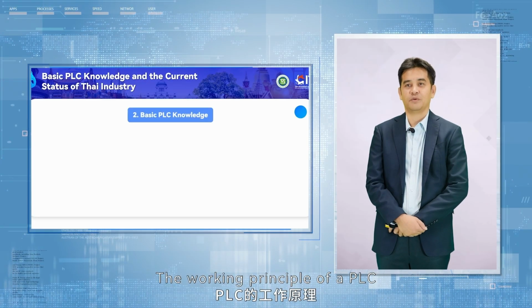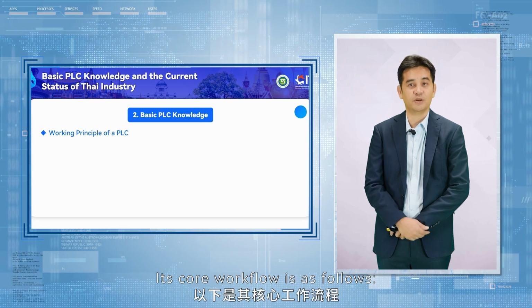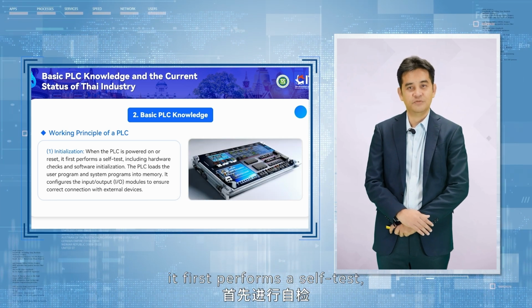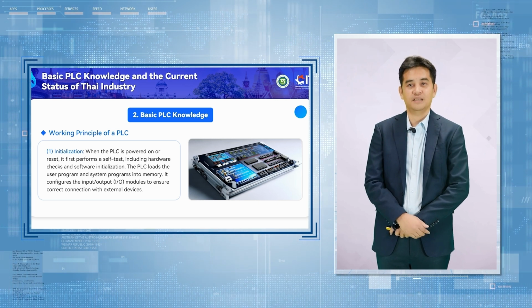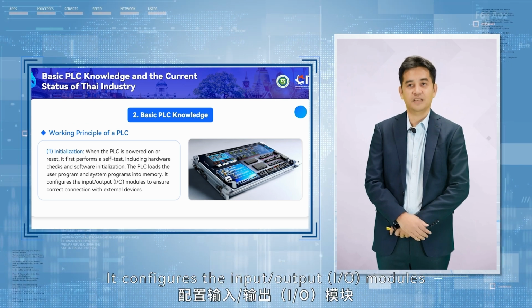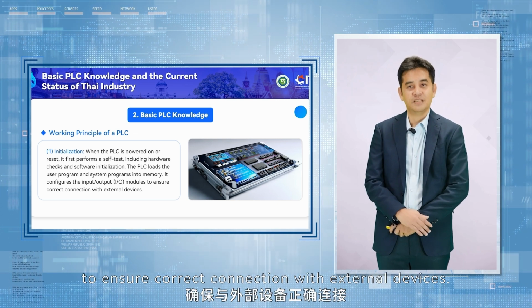The working principle of a PLC is based on a cyclic scanning mechanism. Its core workflow is as follows. 1. Initialization. When the PLC is powered on or reset, it first performs a self-test, including hardware checks and software initialization. The PLC loads the user program and system programs into memory. It configures the input, output, I/O modules to ensure correct connection with external devices.